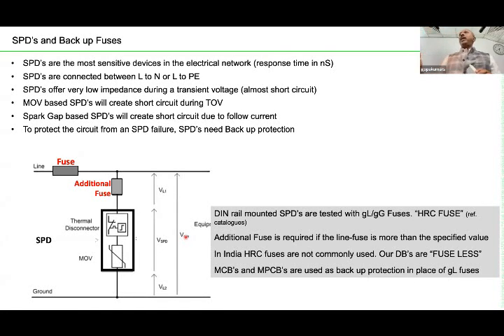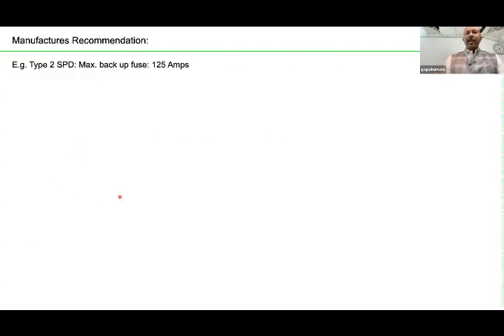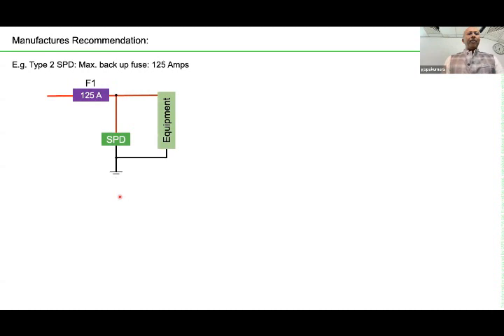Now the user should decide where to put the fuse. Whether he can trust the fuse at the line or you have to have an additional backup fuse. It's a very critical subject. Let us say, for example, you are giving priority to continuity of protection. And this is how it is. You have a 125 amps fuse. That is your backup fuse for your SPD.